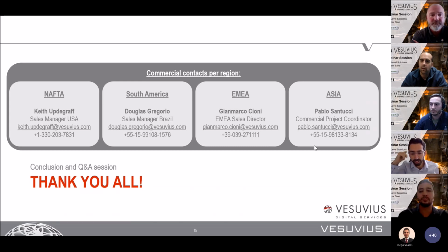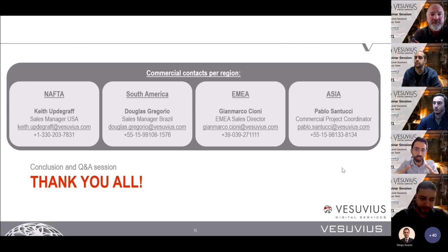Yeah, which reminds me, Garrett, another important point. You have to remember that we are looking at the interface, so basically a line between steel and slag. And depending on where you are in the process, it may not be something completely even and straight. So if you are arcing and blowing and injecting carbon on everything, and everything is shaking there, this line is not going to be extremely precise. So the more steady the furnace, the better. But as Garrett said, in their case, they managed to take an average, and it's actually pretty accurate along the heat. But obviously, the ideal would be to always have the furnace at the same angle.